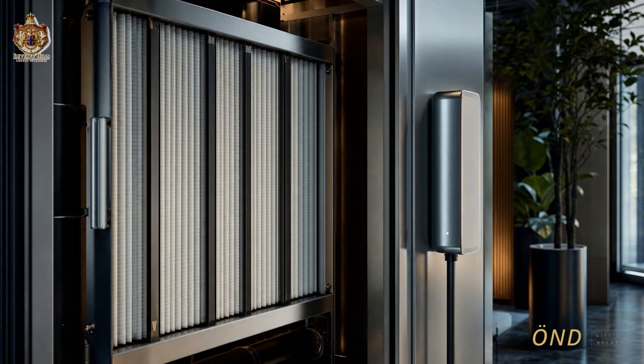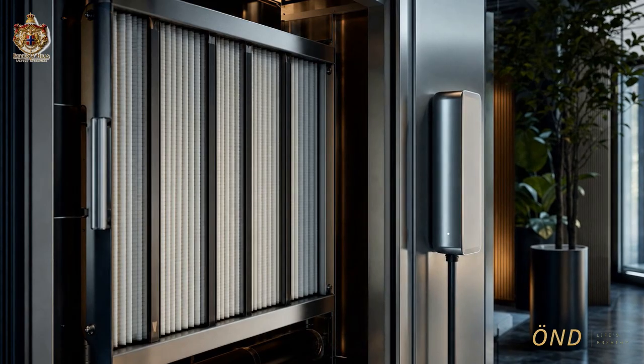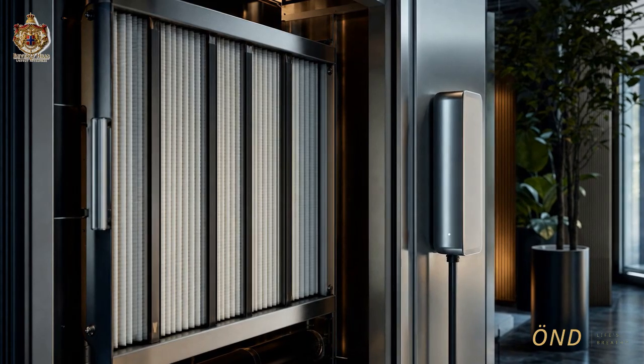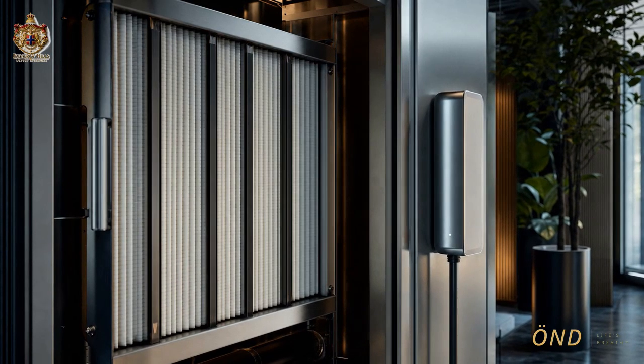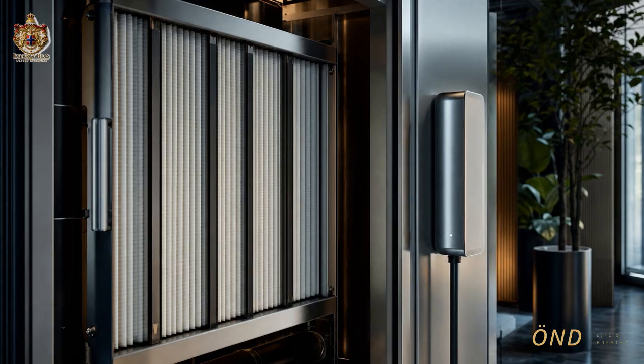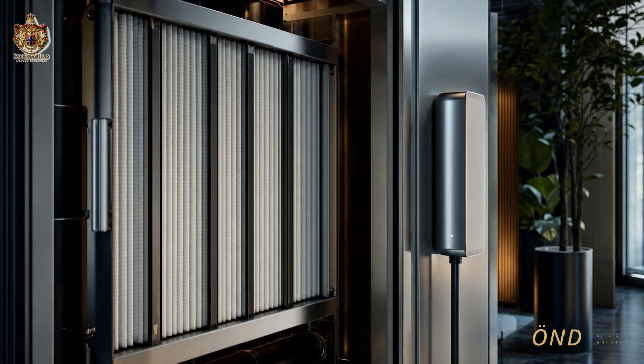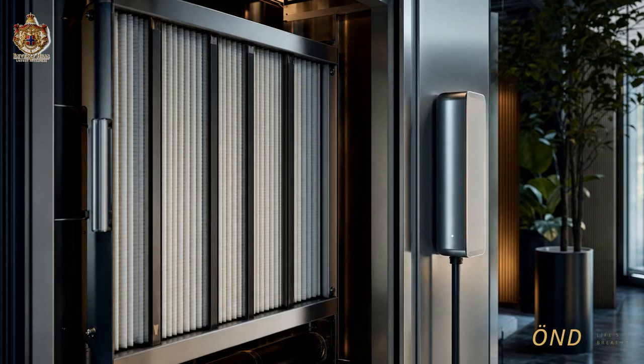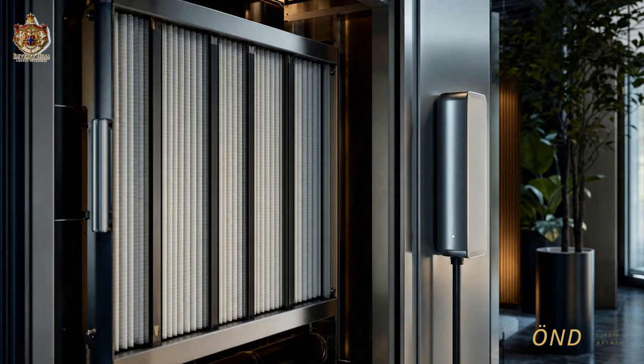Before equipment is ordered, demand a measured baseline. For at least a week, log fine and coarse particulates, carbon dioxide, total volatile organic compounds, formaldehyde, and relative humidity in the rooms that matter most.